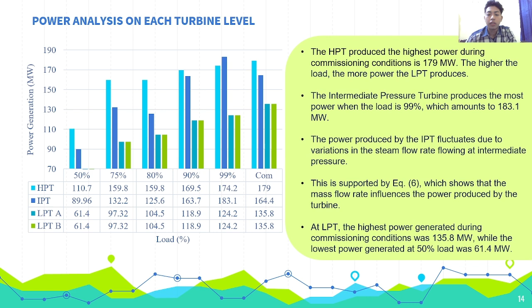The higher the load, the more power the LPT produces. This is a trend line increase. The intermediate pressure turbine produces the most power when the load is 99%, which amounts to 183.1 megawatt. The power produced by the intermediate pressure turbine fluctuated due to variation in the steam flow rate flowing at intermediate pressure.